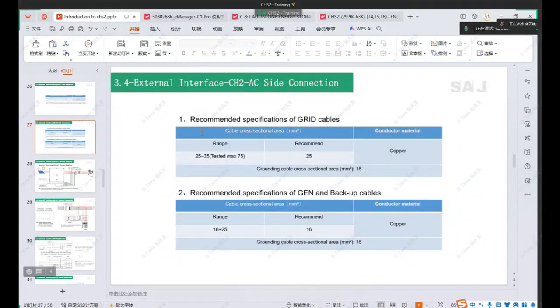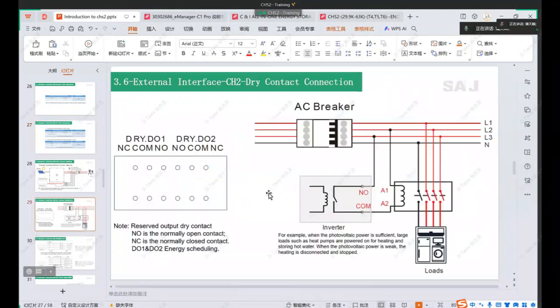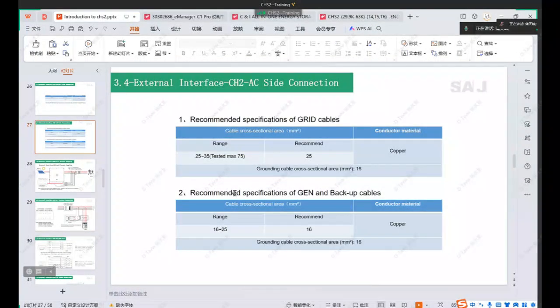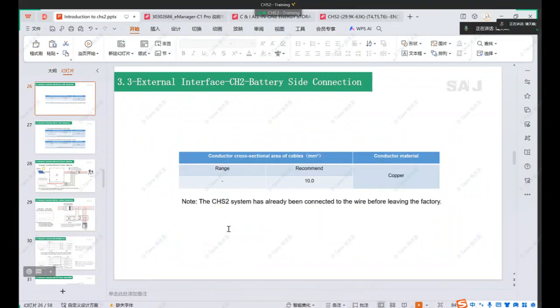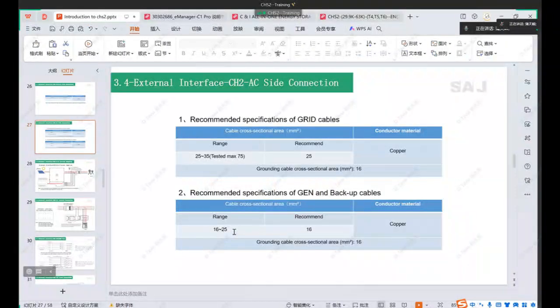And this is for the AC side. AC side, we recommend 25 to 35, but we have tested max is 70, 75, but it's better to use this range, 25 to 35. This is important. Sorry, and the generator and the backup cables recommended is 16 to 25. It's better not more than 25, because if more than 25 it is very difficult to connect the cable. This is important.